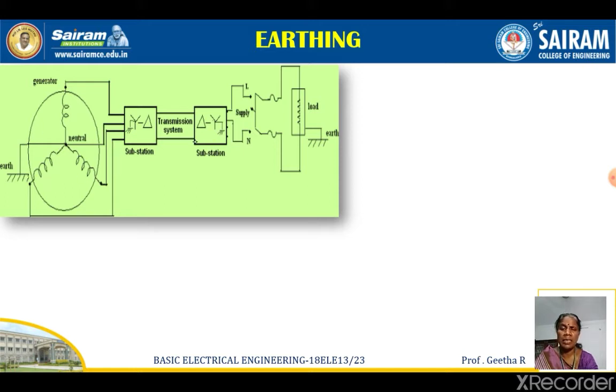Though the neutral line is reaching the customer end, and though it is connected to the earth, it is not sufficient. It has to travel a long distance, so in between there will be conductor resistance. So whatever earthing is given at the neutral point of the generator is not available at the user end or at the load end.